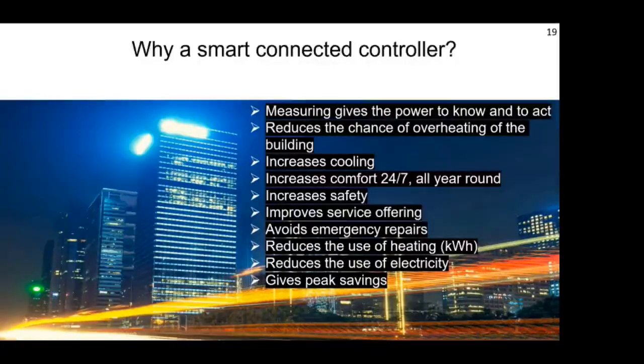Also, the ability to monitor and adjust the substation remotely, with warnings and changes, means preventative works can be carried out at regular maintenance and service intervals. You could notice things changing, pumps not working as efficiently as possible, valves not opening as quickly as possible. That's a good way of going in and checking the system to make sure it's okay. Maybe there's a bit of dirt in the system, maybe a filter needs changing, maybe somebody closed a valve slightly. By knowing that, you're reacting straight away rather than having to get a shutdown. The changes made in real time can also help reduce the kilowatt hours used, meaning the savings start as soon as they're applied remotely, without having to attend site. So it's about understanding what the building is working at via your smart connected controller.